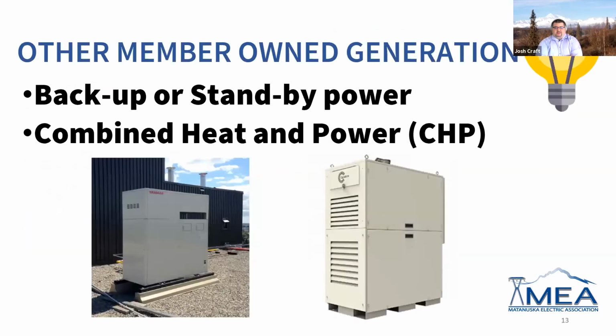Let's move on. There are other types of member-owned generation, like backup or standby power. These situations involve hospitals, or a location that can't go without power. You might have a backup diesel generator or some kind of generator at your house for when the power goes out. There are special interconnection and safety requirements, since this generation cannot be in operation while the grid is up and running. So there's an automatic or manual switch you would have to flip in order for that generation to actually operate your house.